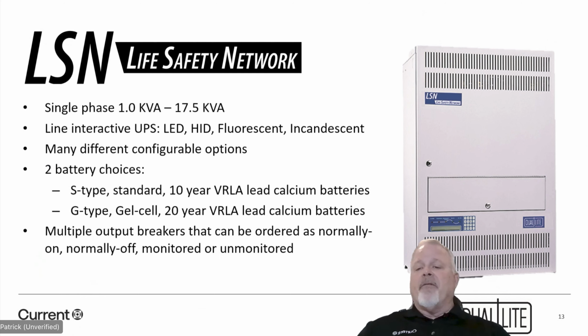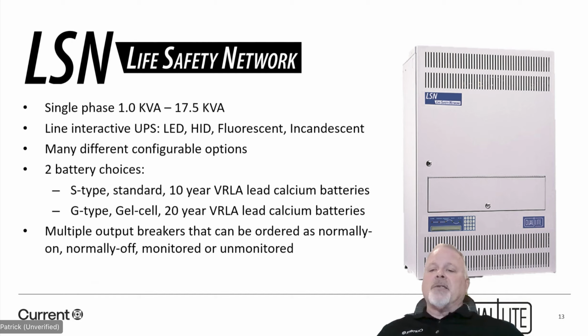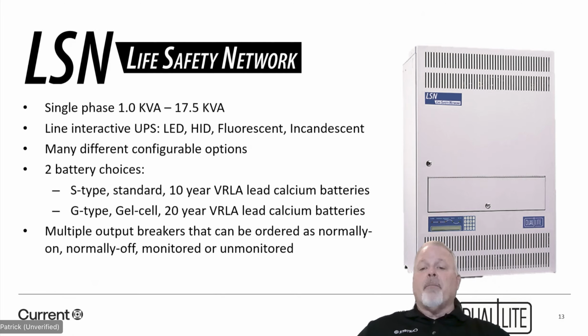2 battery choices. We have our S-type and our G-type. Our S-type is our 10-year VRLA lead calcium battery. These are warranted. And then we also have the G-type, which is our gel cell, which is a 20-year VRLA lead calcium battery. Again, multiple output breakers. They can be ordered as normally on, normally off, monitored, or unmonitored.